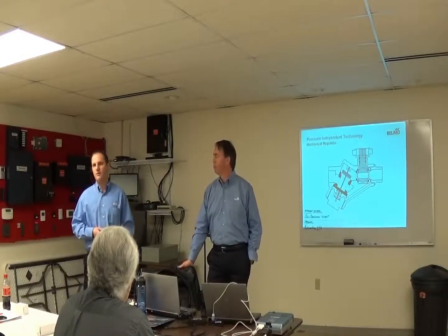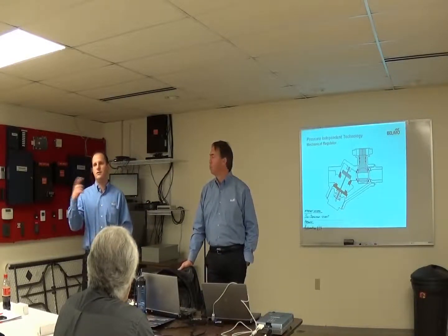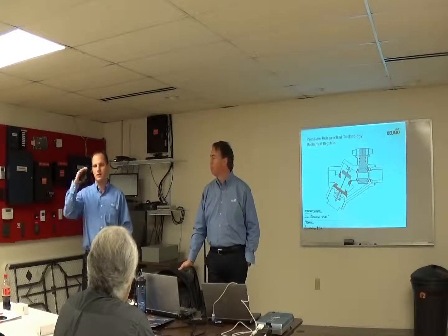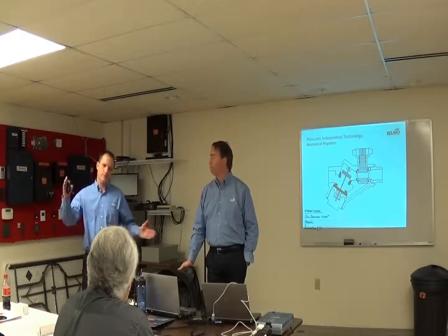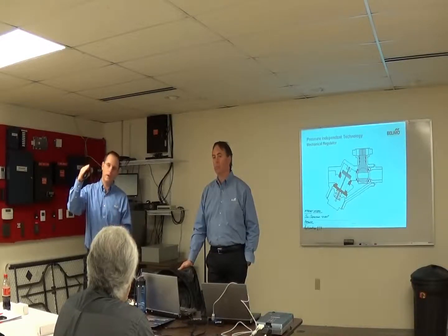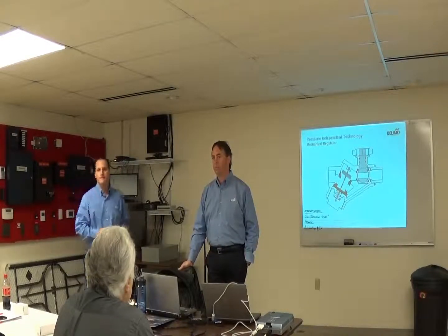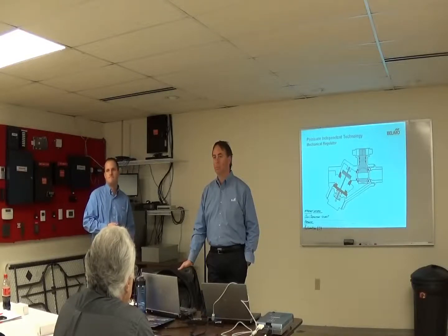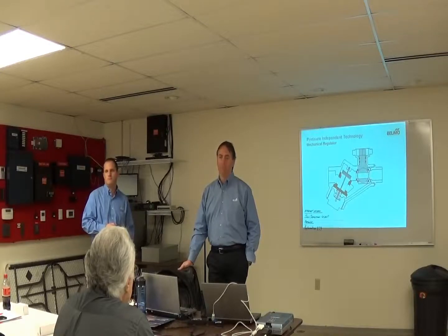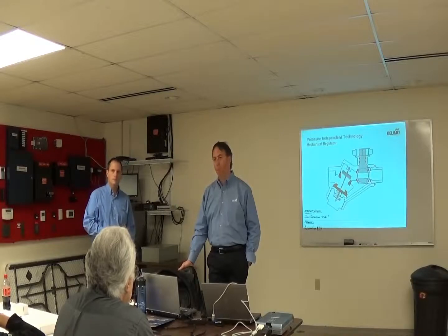And you're using basically flow limiting devices. Yeah, exactly. It's not a flow control. It is limited. You're guaranteeing a max that you won't go over, but under that range you can still be flowing up to that max. Exactly. But my point simply was that, as long as the pressure's within that range, then the valve is doing what it was specified to do. It's limiting at least to that flow. It's not unlike what you're doing here in terms of the balancing situation. If I had bought one of these, I'd just say, check the differential pressure. If it's within 5 to 50, the valve's doing what it's supposed to be doing.